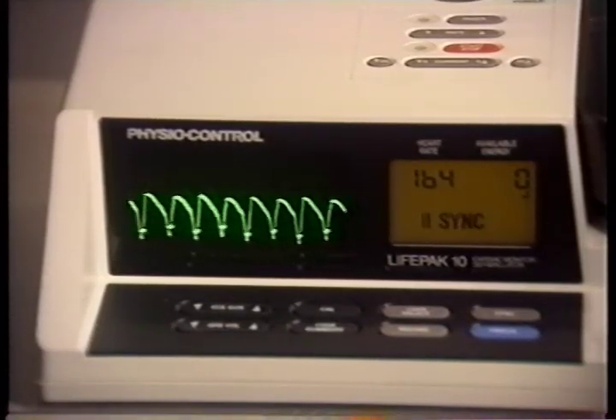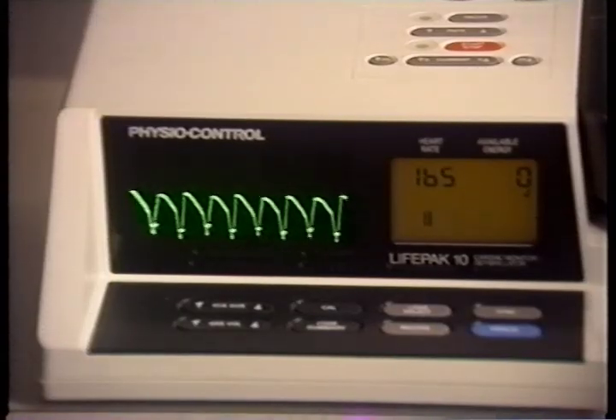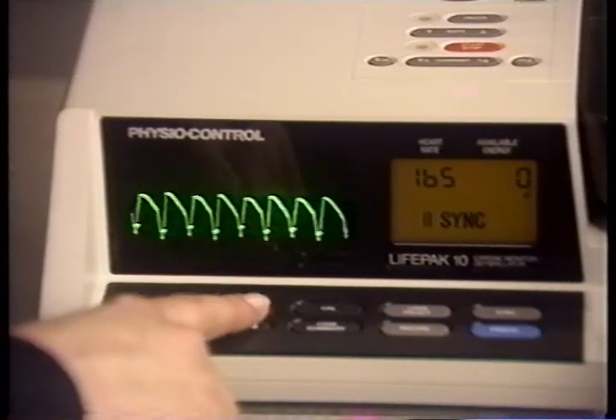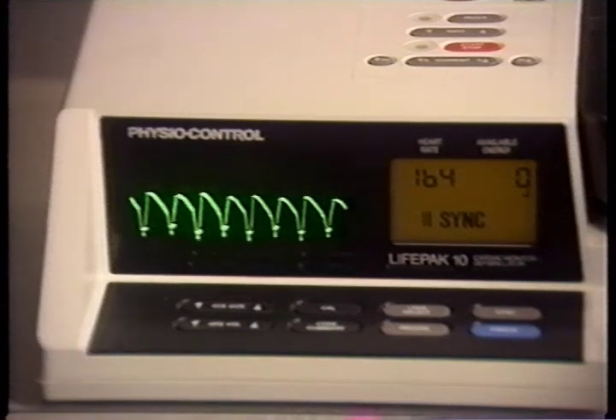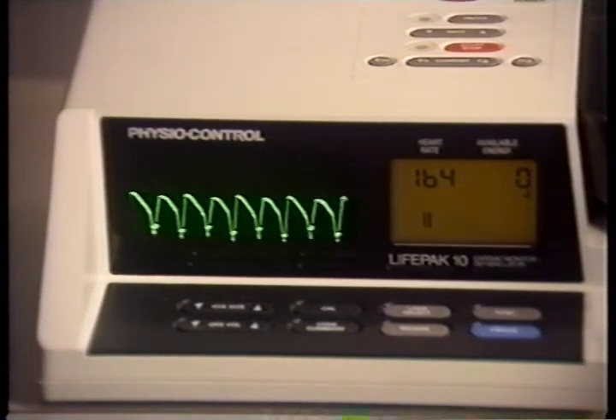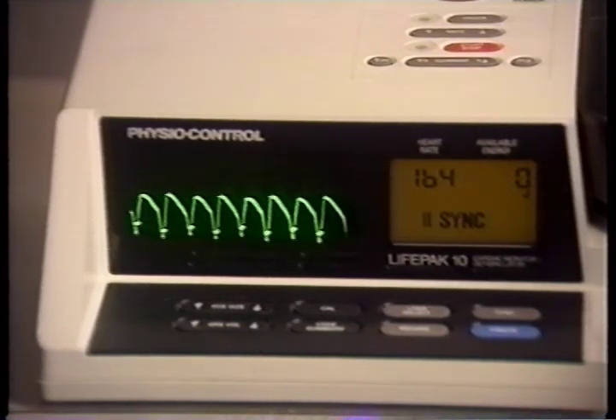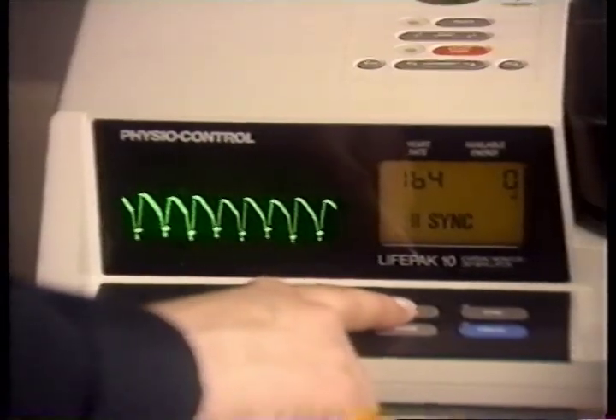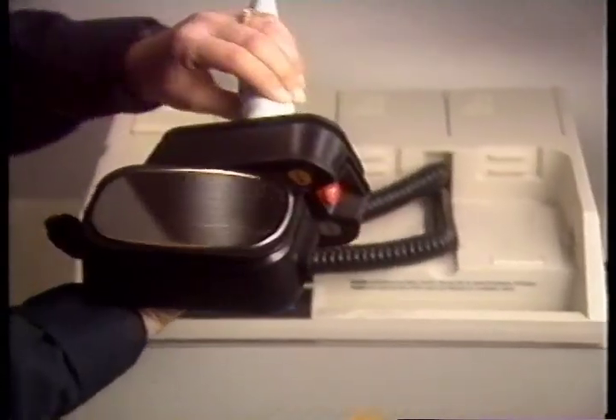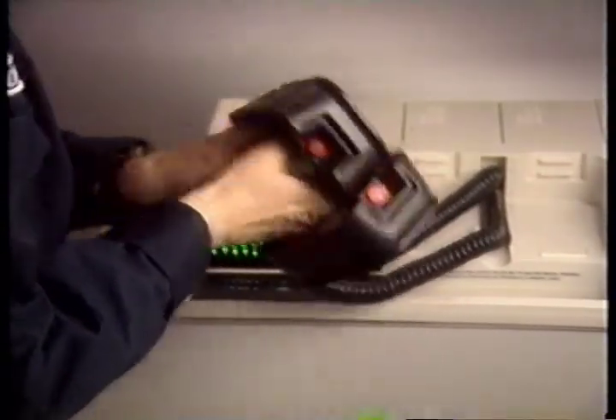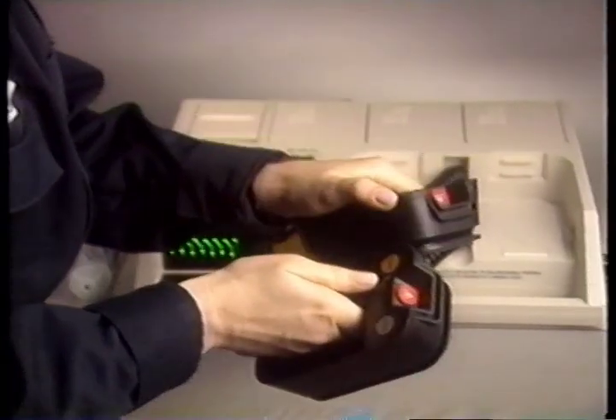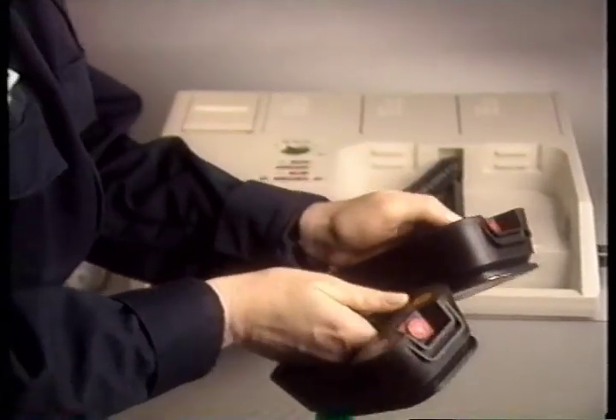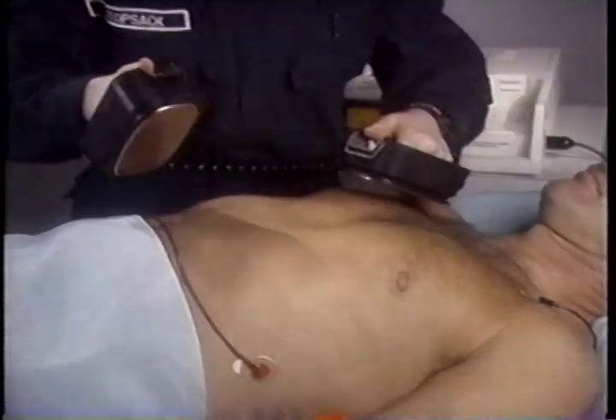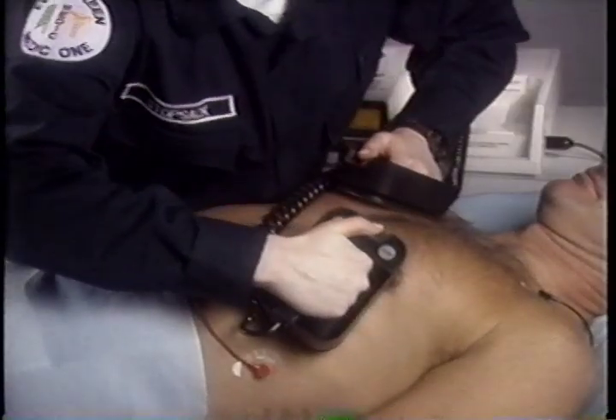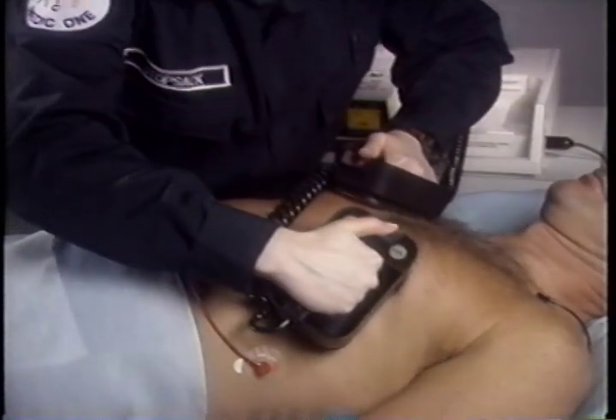If the sync markers do not appear, or appear elsewhere on the ECG, adjust ECG size up or down until they appear on each QRS complex. If adjusting ECG size does not help, select another lead or reposition the ECG electrodes. Apply defibrillation gel to the paddles. Select energy and push the charge button. When the defibrillator is charged, push and hold both paddle discharge buttons until the defibrillator discharges.